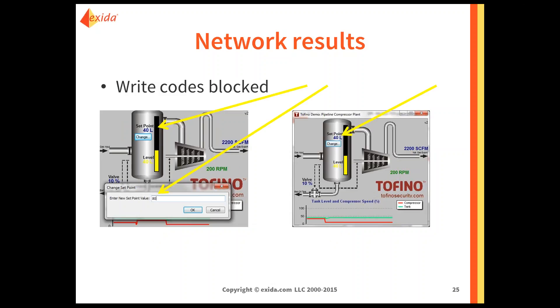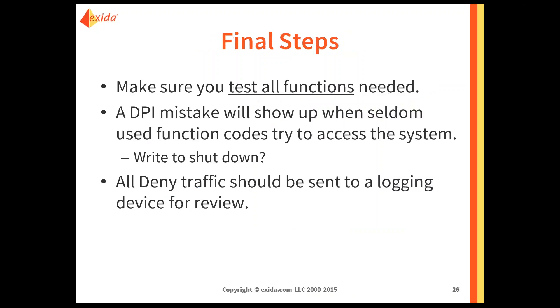But I haven't put any function codes in to allow a write function to be performed. There's a set point setting, and I click the change box to change my set point to 80. When I hit OK and look at the screen, my set point stayed at 40. My write function code was not allowed to pass through to the end device to change the setting — in this case, I didn't want it to.